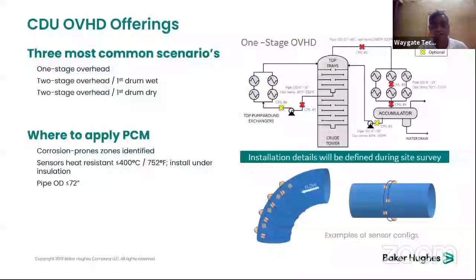As a case study example for crude overhead applications, multiple sensors are needed depending on locations. Examples include bend pipes and normal pipes where sensors are strapped and mounted at each location. Installation design identifies PCM corrosion-prone zones, with sensors heat-resistant to less than 400 degrees at current pipe OD of 72 inches. Higher pipe diameters can be accommodated depending on the severity of the product.